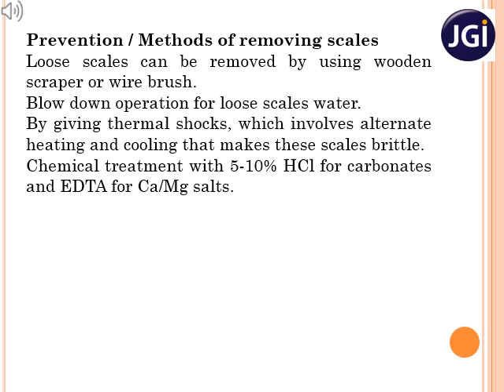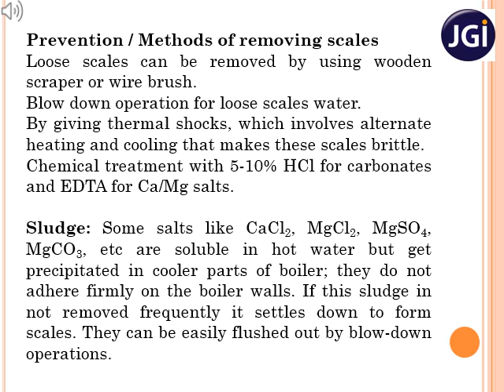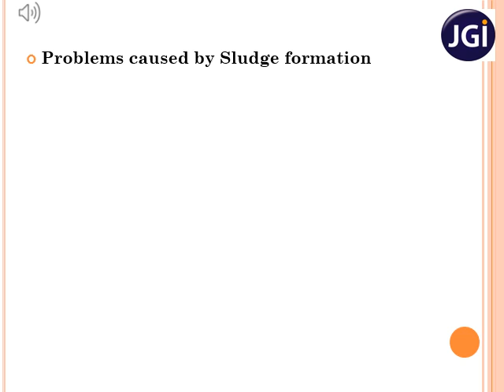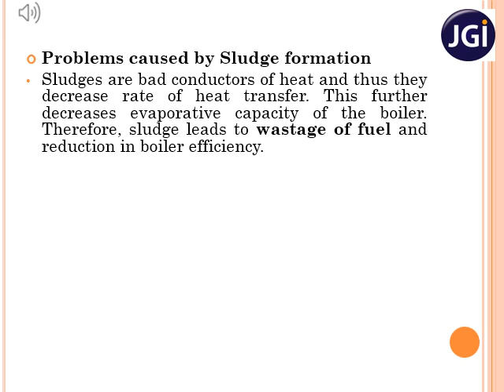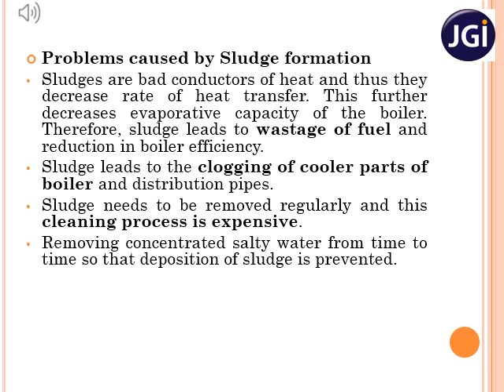We came to know that sludges are soft and non-sticky in nature. Hence, they are soluble in hot water, but they get precipitated in cooler parts of the boiler. If they are not removed, they settle down to form scales. Hence, the sludges are removed by flush operations or blowing air through the boiler pipes. The sludges hinder the heat transfer since they are bad conductors of heat. This leads to the decrease in the fuel efficiency of the boiler. The sludges also lead to blockage of boiler pipes, which is called clogging. The best prevention method is using soft water for the boilers.